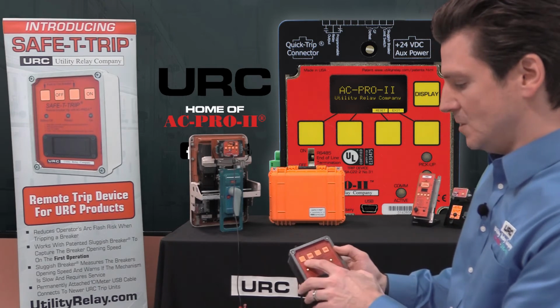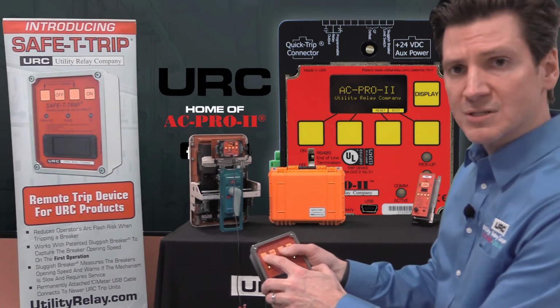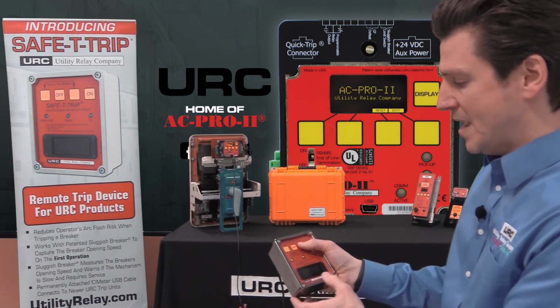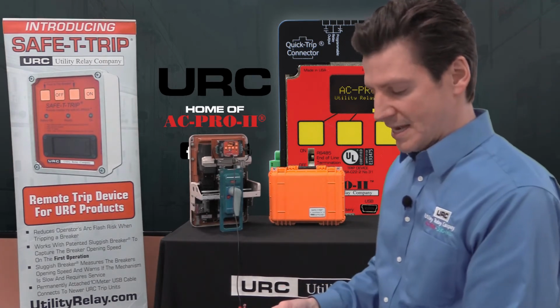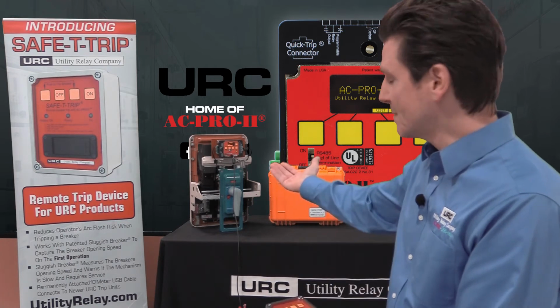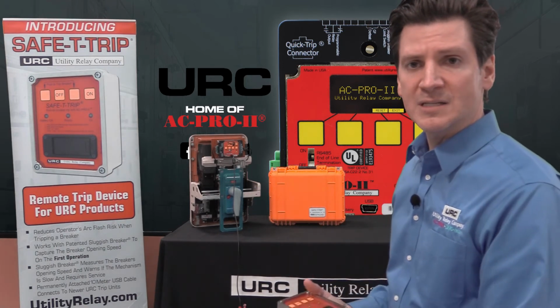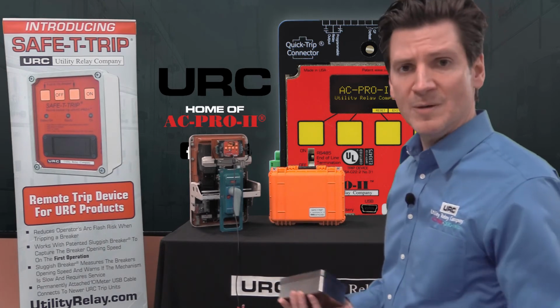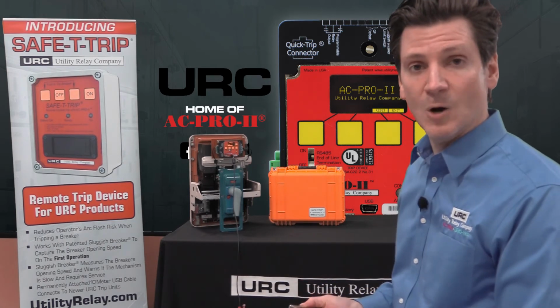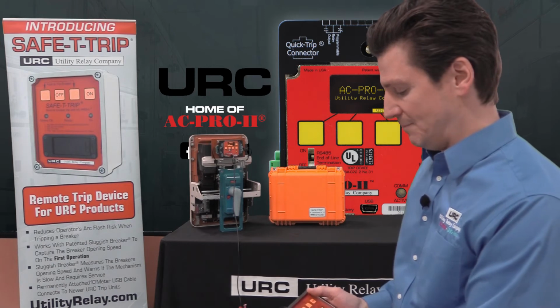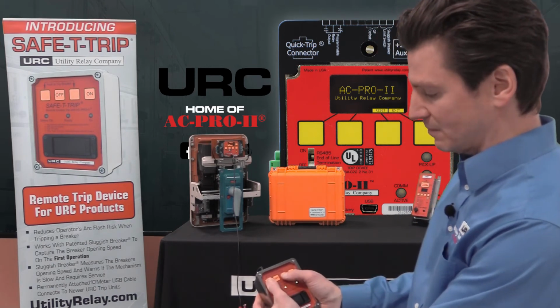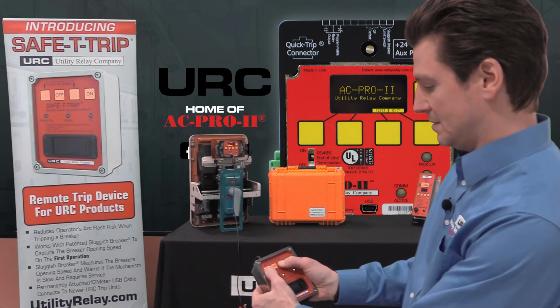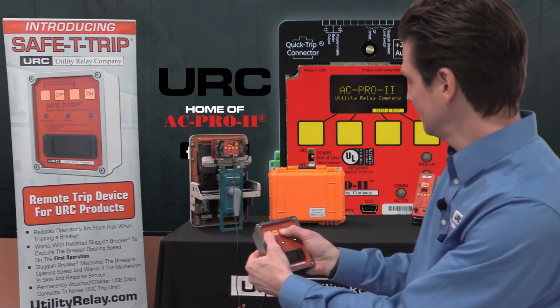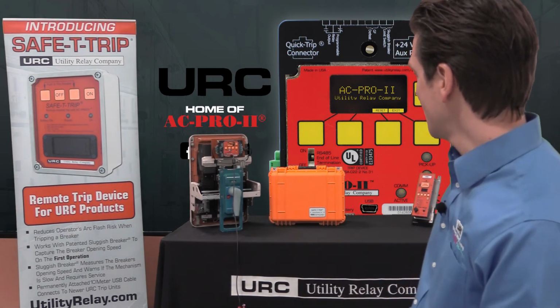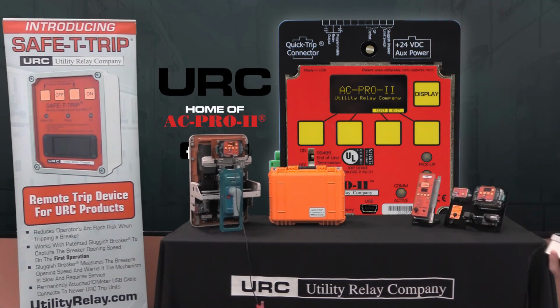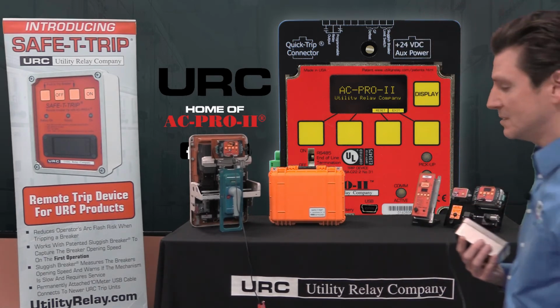You'll notice here too that there are 2 buttons that you need to push simultaneously to trip the breaker. We have that because we don't want somebody to accidentally press just one button and trip the breaker. Maybe a colleague is standing in front of the breaker and they don't know you're going to be opening this, and you didn't even intend to open it. So we want to make sure that doesn't accidentally happen. You have to press both of these buttons together. I'll do that, still on the camera there. There you go. You hear the breaker's opened, and again, I'm standing 30 feet away. If there was an arc flash, I'm completely safe.